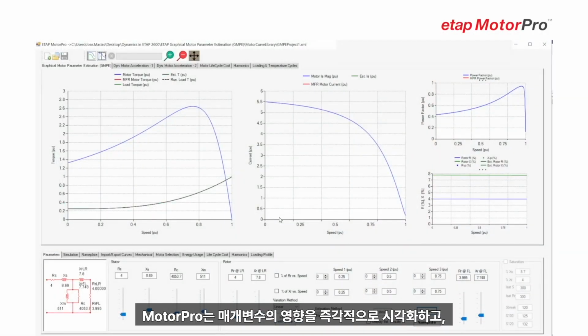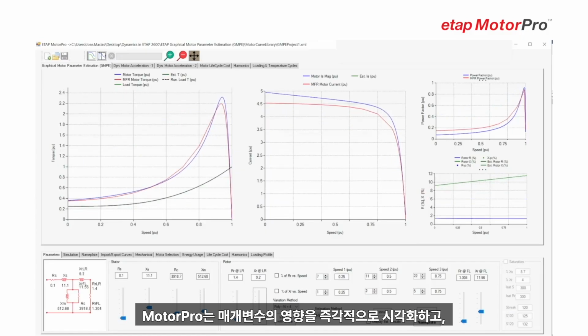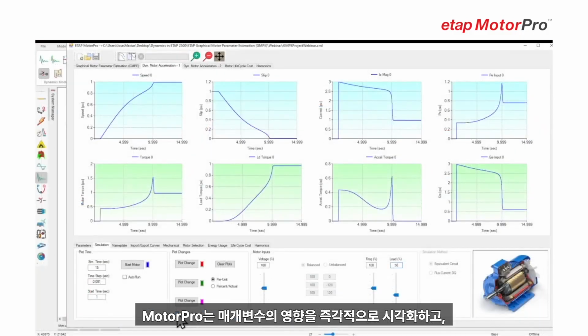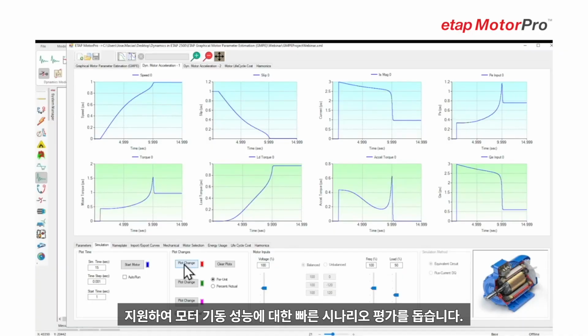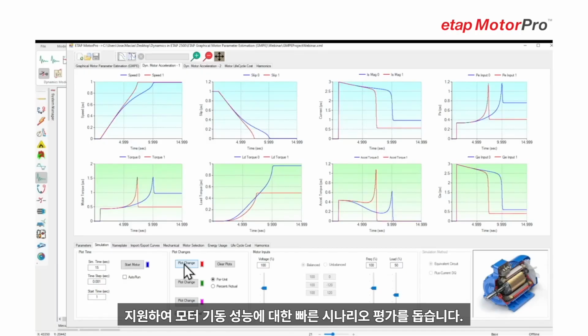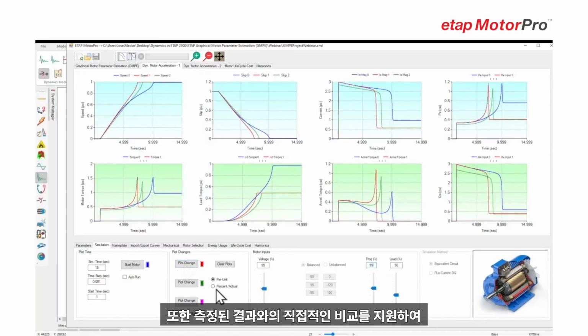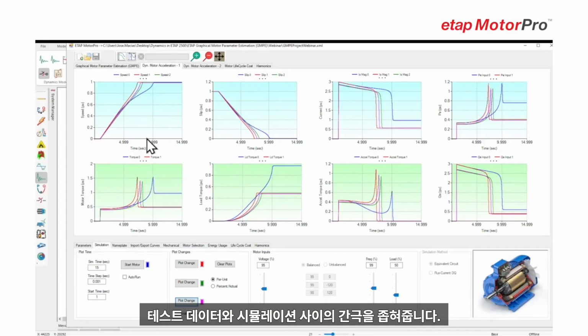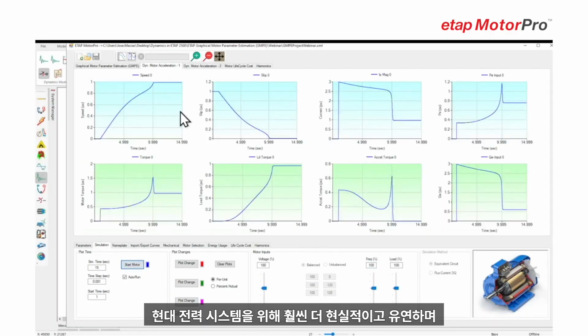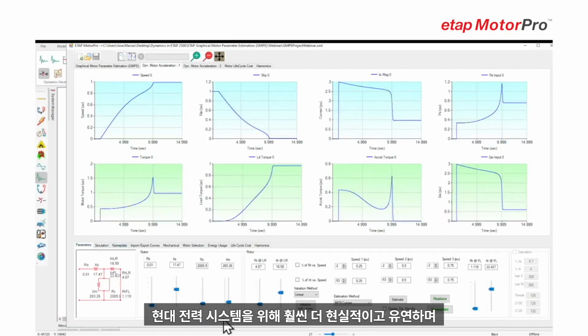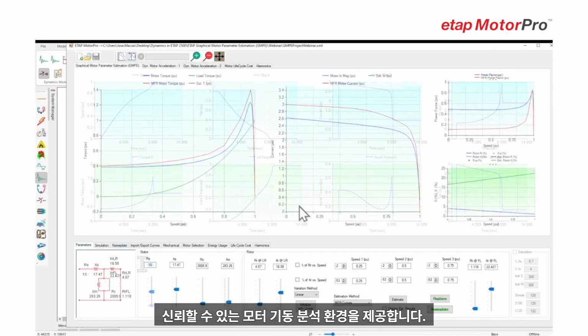MotorPro changes this by enabling immediate parameter impact visibility, supporting incomplete or non-standard manufacturer data without redesign, and allowing fast what-if scenario evaluation for motor starting performance. It also bridges the gap between test data and simulation by enabling direct comparison against measured results, delivering a far more realistic, flexible, and reliable motor starting analysis environment for modern power systems.